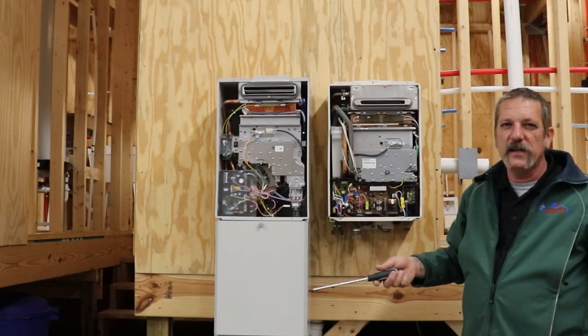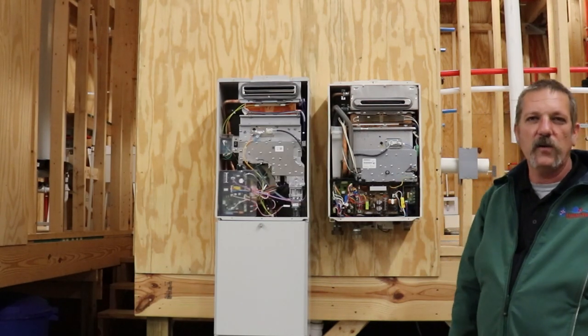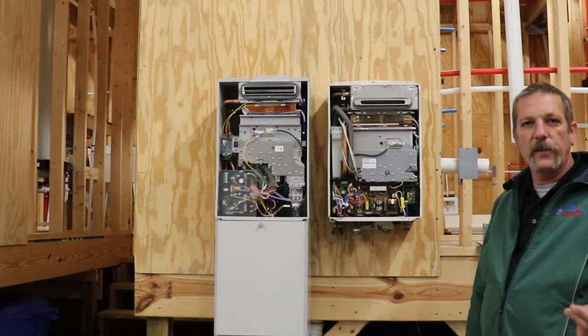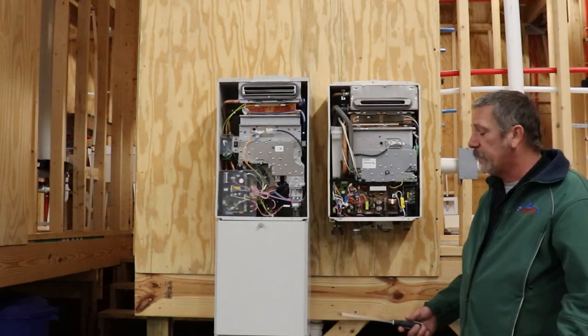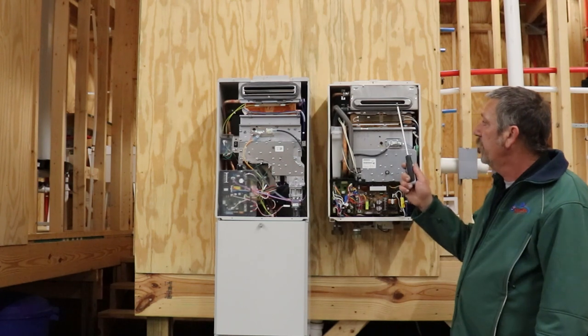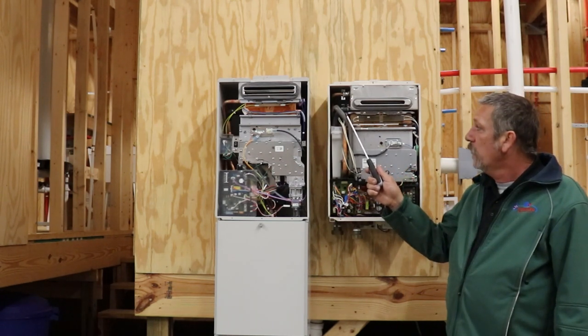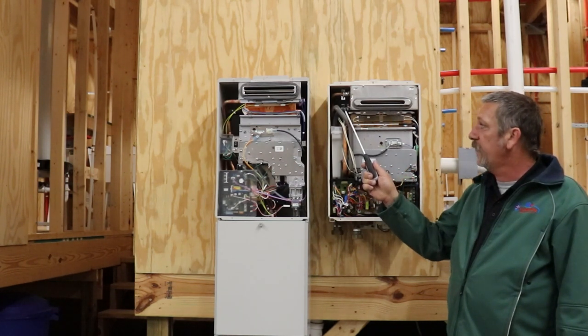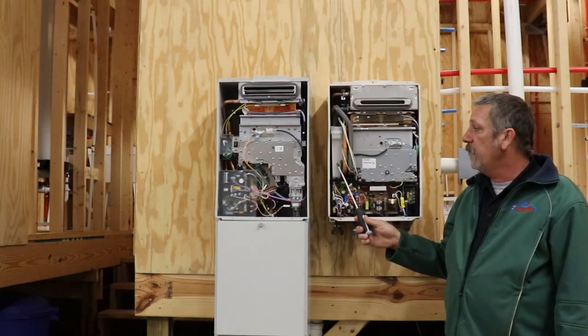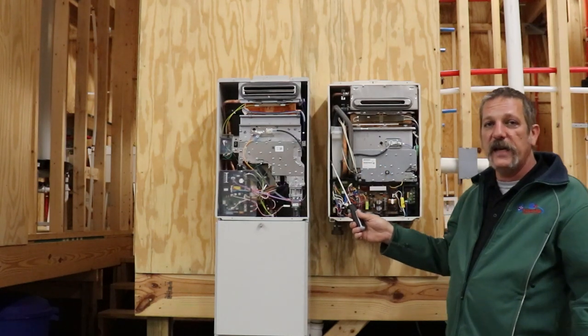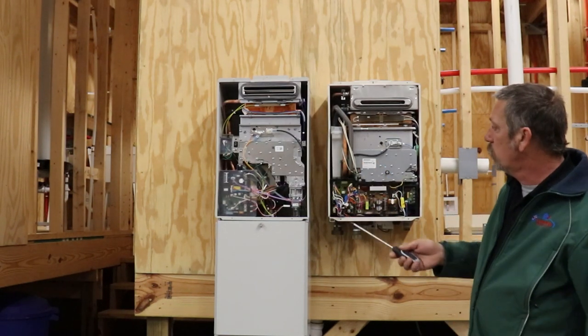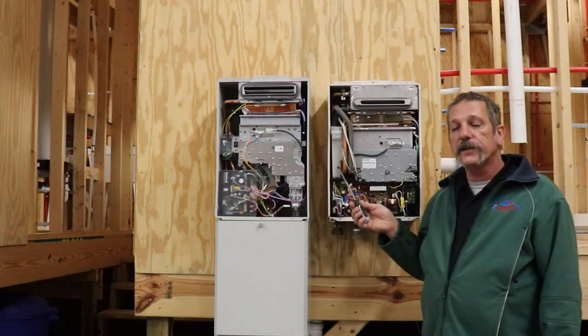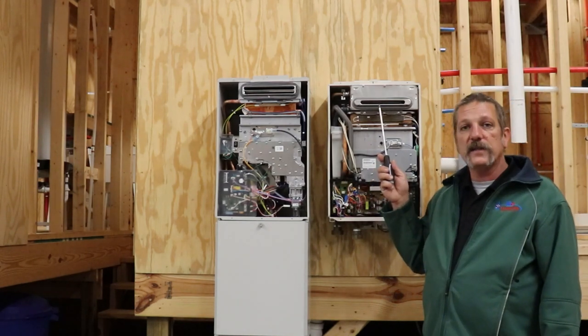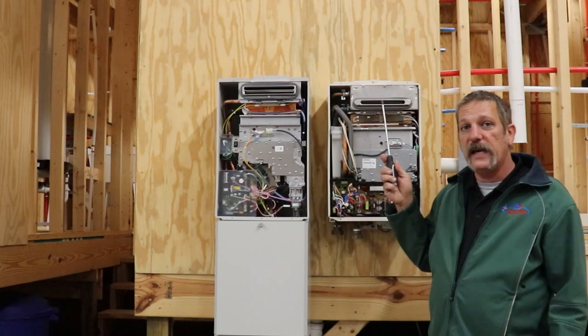It's just like an air conditioner on a house or an air conditioner on your car. It's gonna have a little bit of water dripping off of it. And that's perfectly normal, perfectly fine. It's got a little drain over here that picks that water up, a little pan that catches that water, and it puts it down into here, which is kind of like a P-trap. It's a little thing that holds the water. They call it a neutralizer. Because this condensate is actually a little bit acidic.